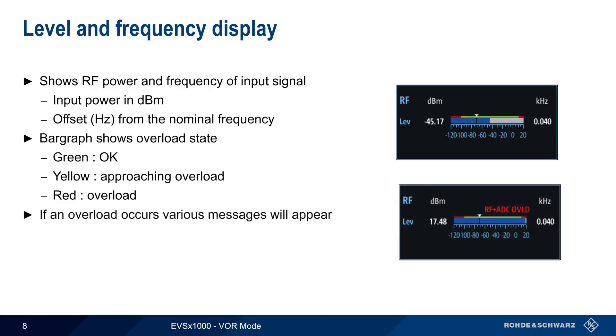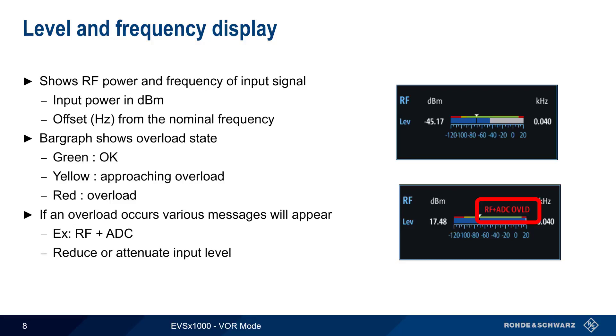If an overload condition does occur, different messages will appear depending on the type of overload — for example, both RF and ADC overloads. Regardless of the cause of the overload, the solution is to reduce or attenuate the input level, and this can be done by setting RF attenuation to either normal or low distortion. Please see the EVS1000 General Overview presentation for more details on configuring RF attenuation.